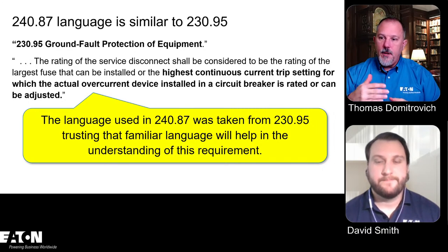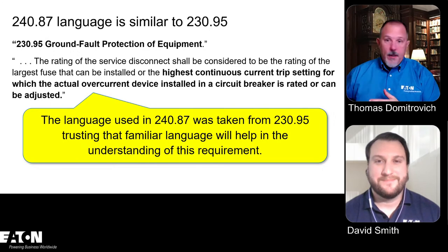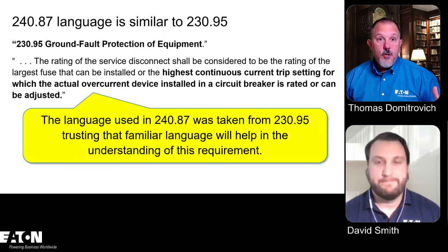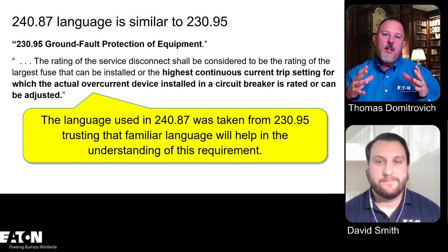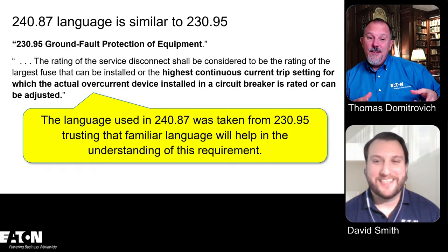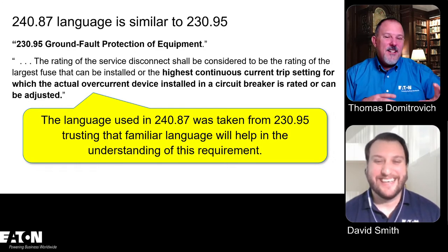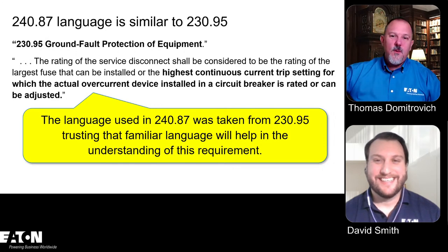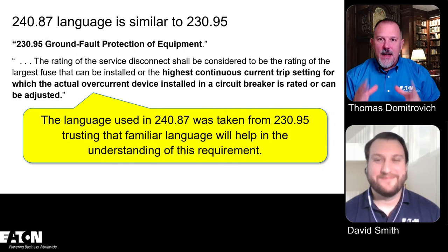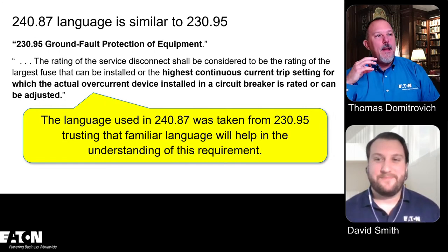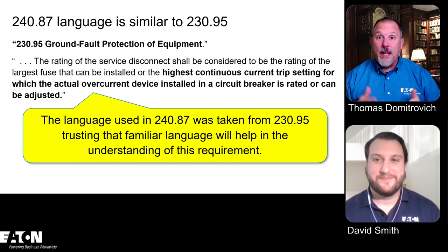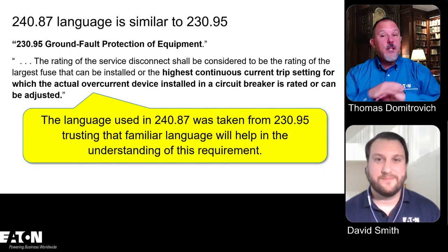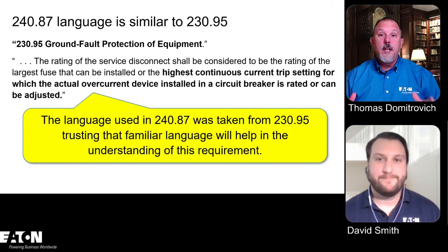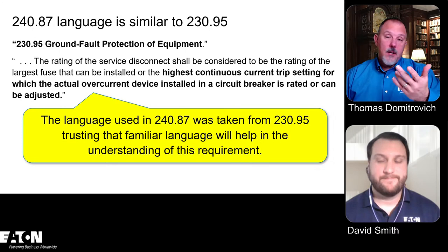Well, at some point, you're going to be into a power circuit breaker. And when you get into a power circuit breaker, you're into switchgear. Yep. You're into big equipment. So they wanted something that was not a power circuit breaker. Like Goldilocks, right? This one was too soft. This one was way too hard. They needed something that was just right. And they found it in the insulated case circuit breaker. And instead of just calling it a molded case circuit breaker, like they should have, hindsight being 20/20, they should have just called it a 3,000 amp molded case circuit breaker with a 30 cycle delay up to a certain fault current. But they called it an insulated case.